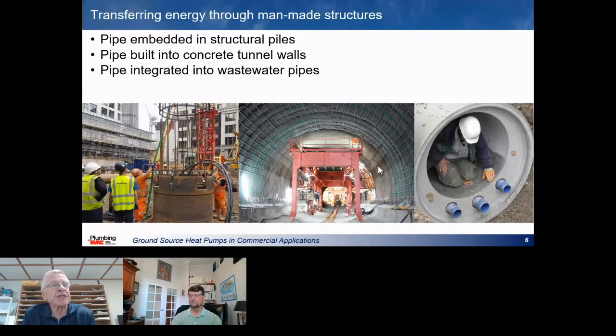Photograph on the left shows a pipe being installed in piles under a building in downtown New York, in Manhattan. There's a quarter million square foot building connected to these piles, and just the pipe in the piles provides about 40% of the heating and about 30% of the cooling for that building, and that is supplemented by an air source heat pump. Systems have been installed, pipes have been installed in subway tunnels or in wastewater pipes, a lot of different ways. As long as you can contact the dirt with the pipe, you can transfer energy.